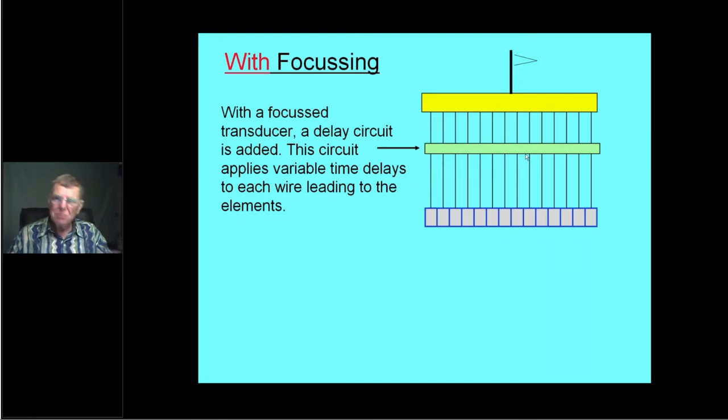So I'll mention beamformer again a couple of times. The beamformer is a circuit within your ultrasound machine that looks after the individual energy spikes going into the individual transducer elements and the timing of them.